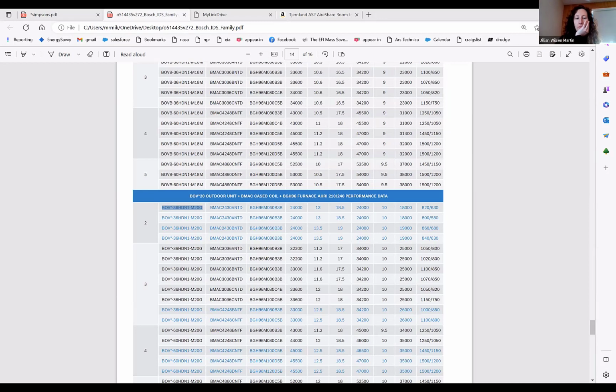For your home, where there's a centrally ducted furnace and AC in the basement, one zone thermostat centrally located on the interior wall of the first floor, with a heat load of 32,000 BTUs per hour, the two options that stand out: from an Asian manufacturer like Mitsubishi, I could put in a 30,000 BTU ducted system. Looking at its performance, it starts at 34,000 and drops to 32,000, so at 5 degrees it's right on the heat load. That could be a really good approach.